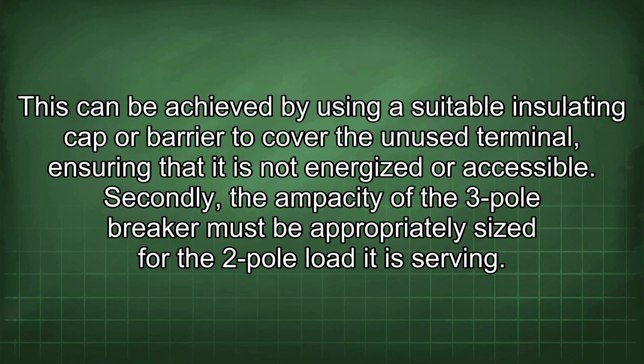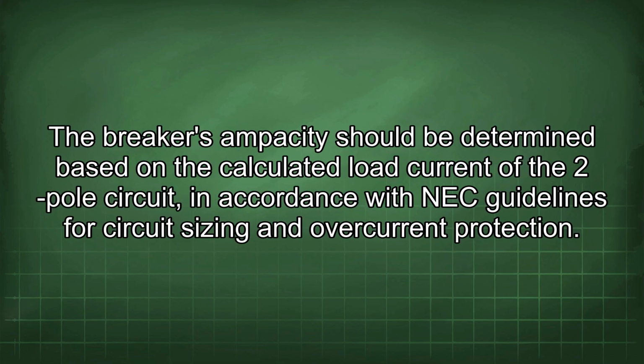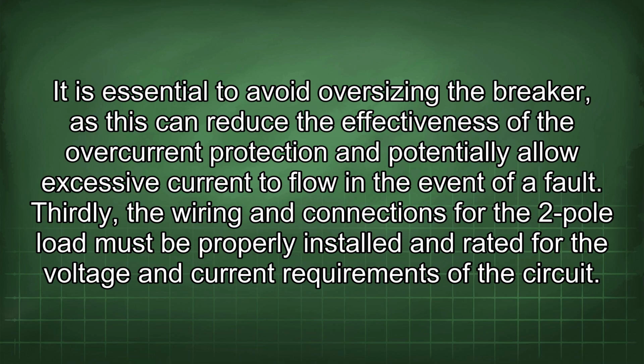Secondly, the ampacity of the 3-pole breaker must be appropriately sized for the 2-pole load it is serving. The breaker's ampacity should be determined based on the calculated load current of the 2-pole circuit, in accordance with NEC guidelines for circuit sizing and overcurrent protection. It is essential to avoid oversizing the breaker, as this can reduce the effectiveness of the overcurrent protection and potentially allow excessive current to flow in the event of a fault.